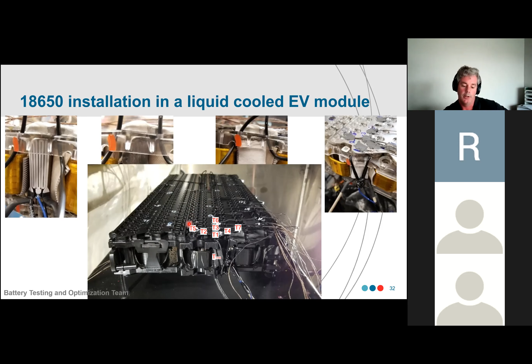These liquid cooled systems are difficult to test at the module level because any heating source tends to wick heat away. So our method was really able to show how you could still trigger thermal runaway in these liquid cooled systems. And that has a big effect on the results of the test. Because if you run the test without liquid cooling here on the left, and you compare it to a test with liquid cooling, you'll see in a moment very different results.